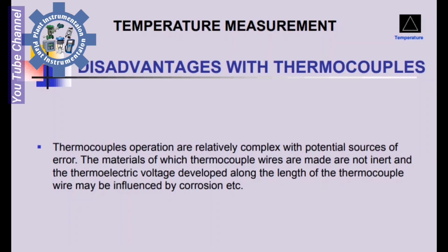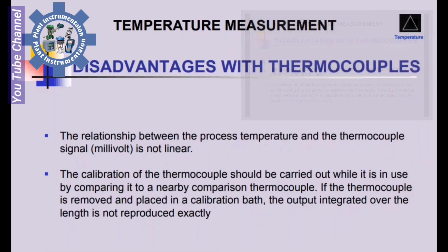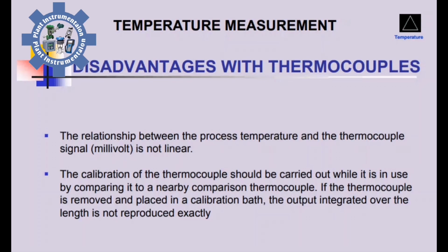Thermocouple operations are relatively complex with potential sources of error. The materials of which thermocouple wires are made are not inert, and the thermoelectric voltage developed along the length of the thermocouple wire may be influenced by corrosion. The relationship between the process temperature and the thermocouple signal in millivolts is not linear. The calibration of the thermocouple should be carried out while it is in use by comparing it to a nearby comparison thermocouple. If the thermocouple is removed and placed in a calibration bath, the output integrated over the length is not reproduced exactly.